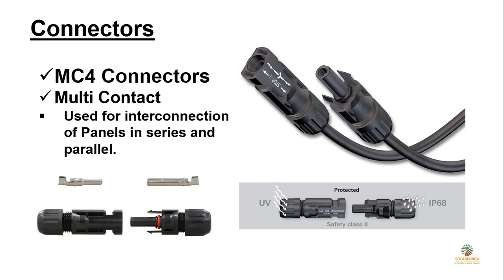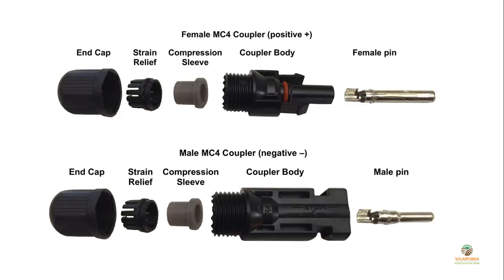The male and female connectors interlock when connected to each other. MC4 connectors are UV protected and have an IP68 rating, so they are waterproof and dustproof. The components of an MC4 connector include: an end cap, strain relief, a compressive sleeve which holds the input cable, a coupler body, and male and female pins. The input cable gets attached to the pin, which locks into the coupler body. With this, you are ready to interconnect solar panels in series and parallel.